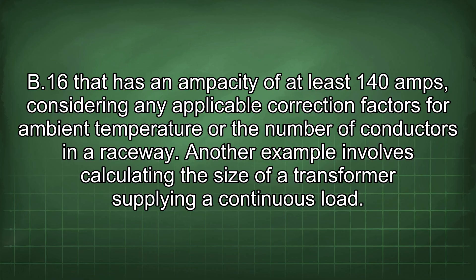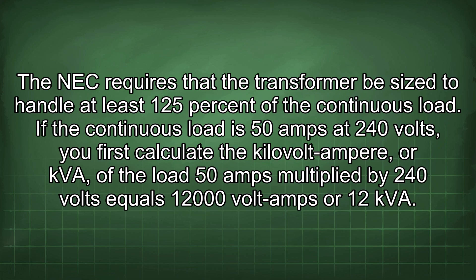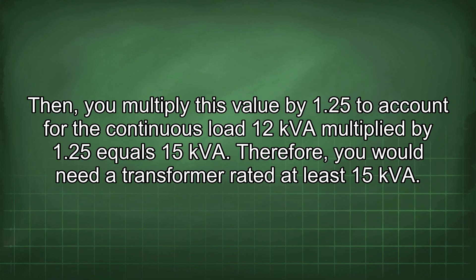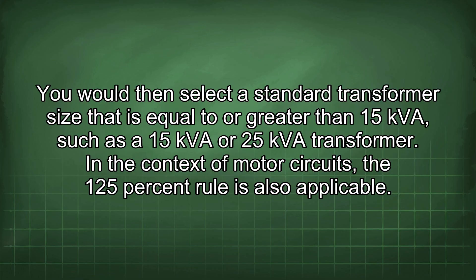Another example involves calculating the size of a transformer supplying a continuous load. The NEC requires that the transformer be sized to handle at least 125% of the continuous load. If the continuous load is 50 amps at 240 volts, first calculate the kVA of the load: 50 amps × 240 volts = 12,000 volt-amps or 12 kVA. Then multiply by 1.25: 12 kVA × 1.25 = 15 kVA. Therefore, you would need a transformer rated at least 15 kVA, such as a 15 kVA or 25 kVA transformer.